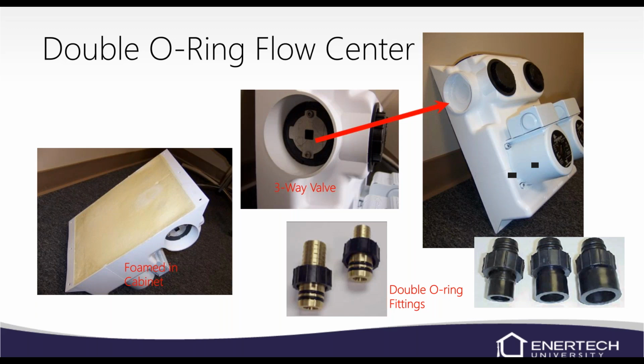One thing I will say about flow centers, especially pressurized flow centers when they're new, you get someone who has one that's leaking right off the bat. A lot of times what I see is it's when the loop field piping comes in the top, which doesn't really matter. You can turn these flow centers whichever way you need to, but I see that the loop field pipes don't come in straight. Maybe one of them's kicked off just a tiny bit and it doesn't want to seal right. And what happens is that water will actually come out the top and run through the back, and it'll look like the flow center is leaking because you can't see it leaking from anywhere else, just back behind that foam.